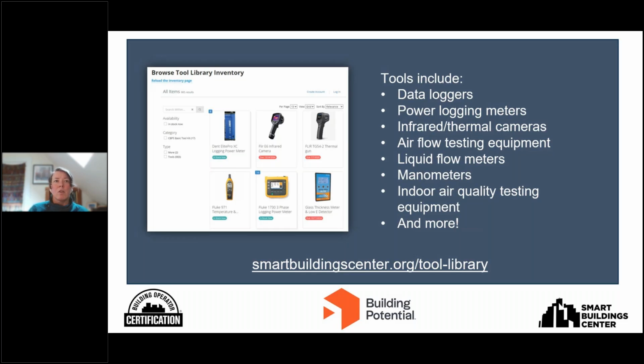We also have a lot of different types of airflow testing equipment, for flow and pressure. We have instruments with pitot tubes that you can use to look at airflow or velocity in ductwork, as well as at grills, and we have flow hoods. We also have non-invasive liquid flow meters, clamp-on ultrasonic flow meters that can detect flow as well as temperature in water pipes. Those are very useful for a lot of different applications: boiler systems, chiller systems, hot water systems, etc.